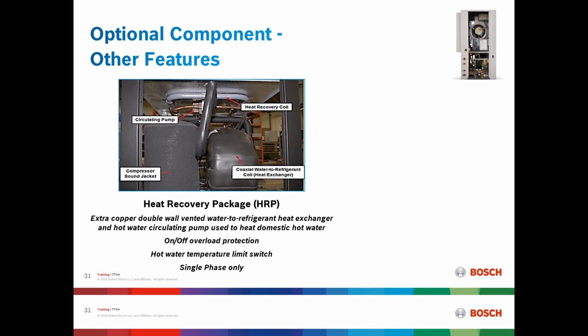Another optional feature will be the heat recovery package or HRP. This device is an extra copper double-wall vented water to refrigerant heat exchanger in a U shape, shown at the top of the photo. And it also has a hot water circulating pump equipped with it to assist in heating domestic water with bypass heat off the compressor. This particular feature has an on-off overload protection. It has a hot water temperature limit switch and is available in single-phase power only.